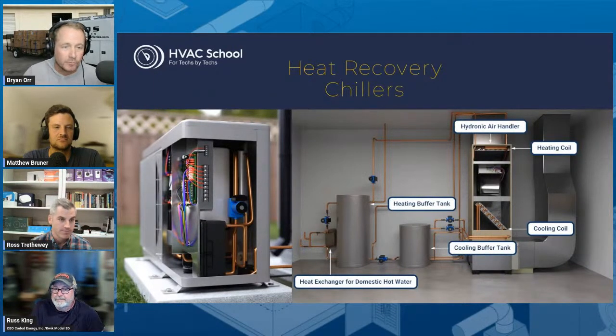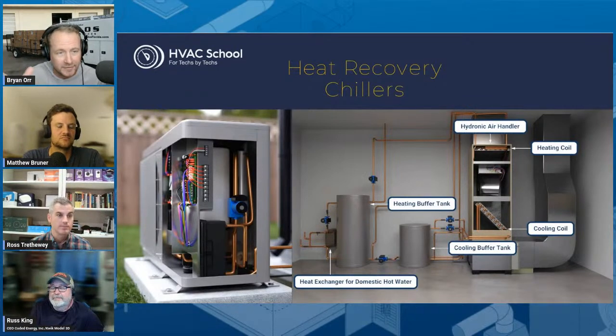Yeah, and this can work with radiators. You could even do radiant cooling with this type of system if you used mixing, so that way you could actually keep it to a point that you're not hitting dew point in cases where that's advantageous. There's lots of things you can do. You can do floor heating. I mean, you can go on and on and on.